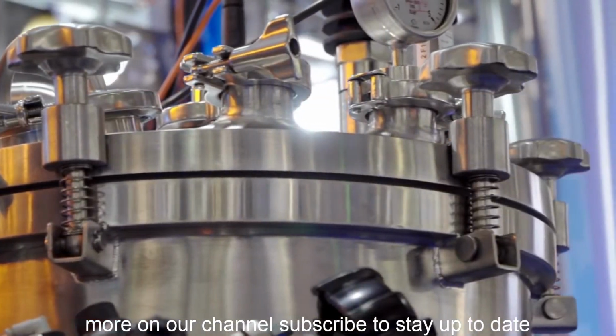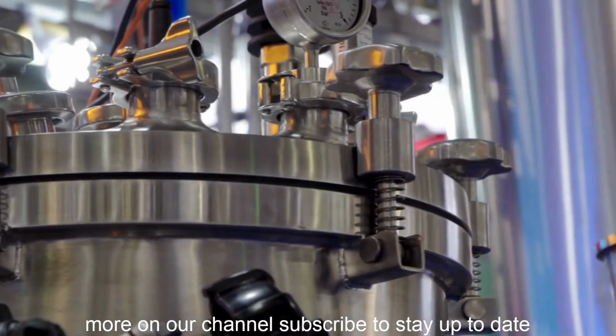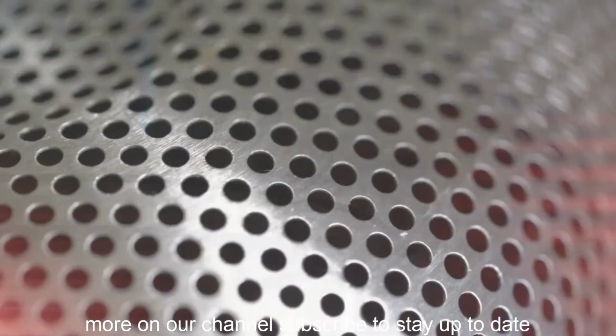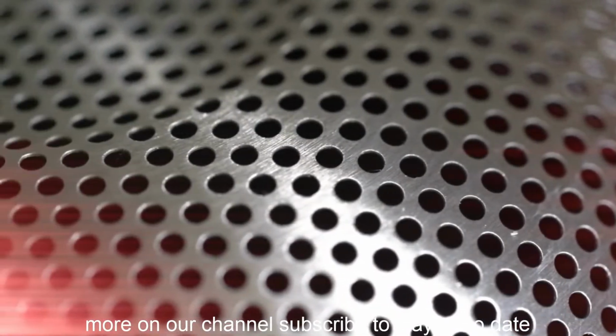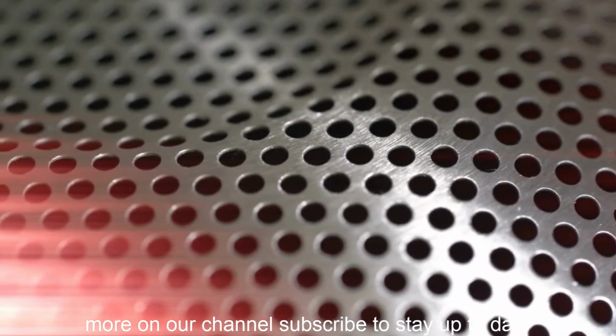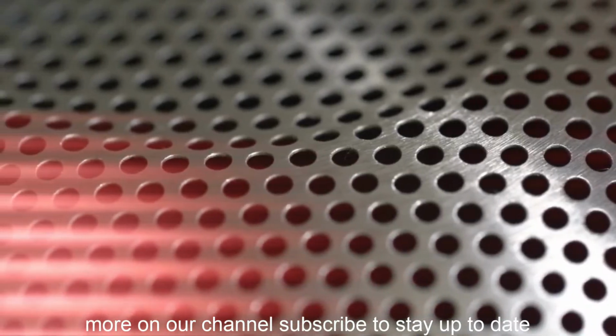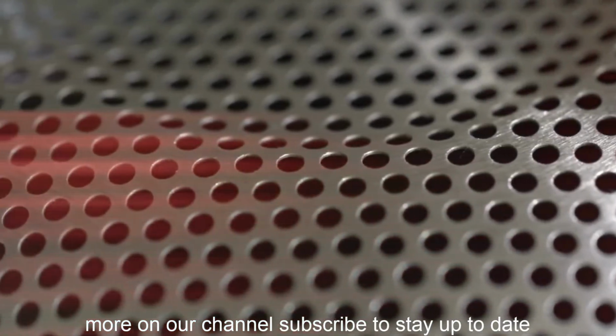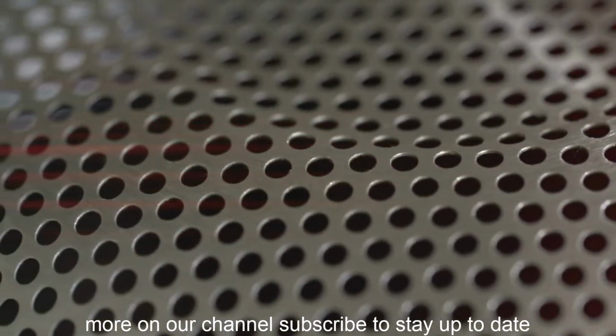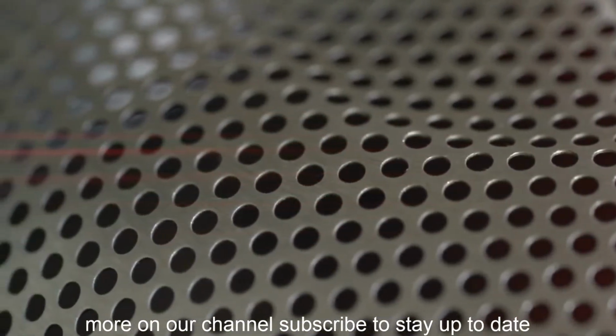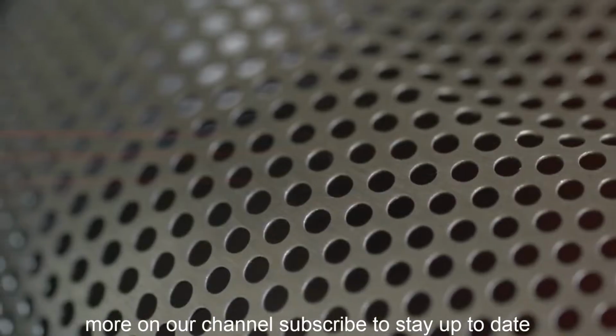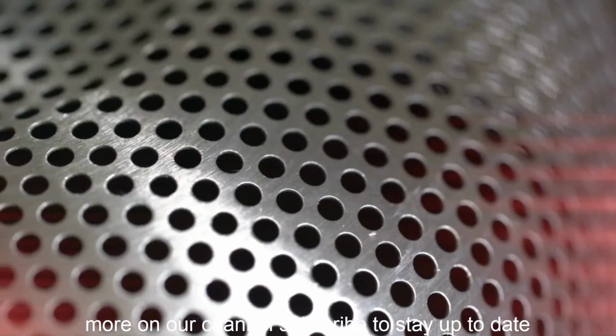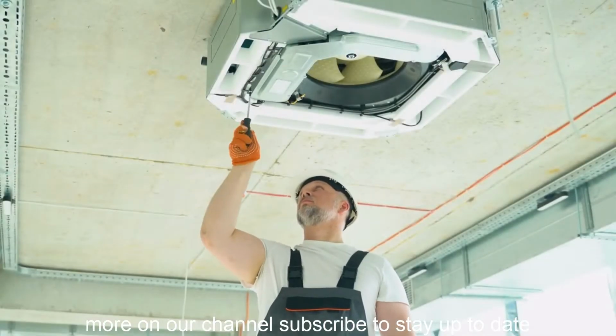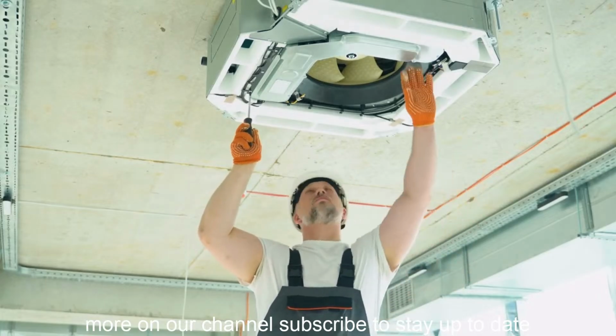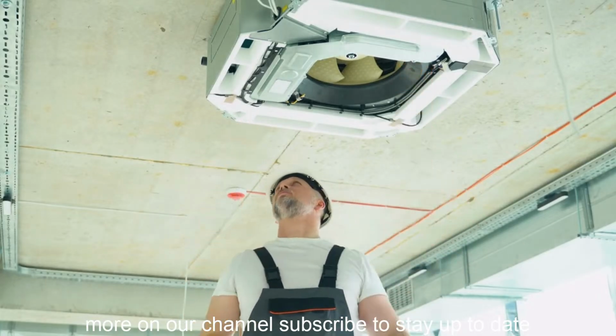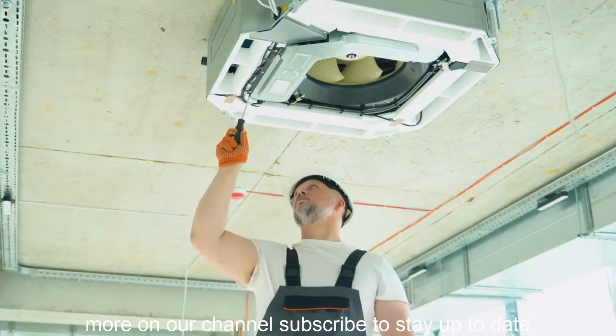Utilities like water systems, purified water, water for injection, and HVAC, heating, ventilation, and air conditioning, are integral to the facility and must be designed, installed, and maintained to prevent contamination and control environmental conditions like temperature, humidity, and air quality. For example, in a sterile manufacturing area, the HVAC system uses HEPA filters to remove particulates from the air and maintains positive air pressure to prevent unfiltered air from entering.